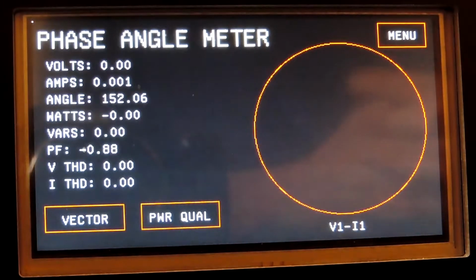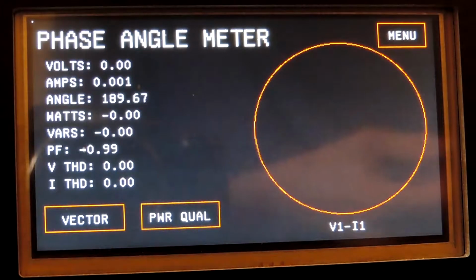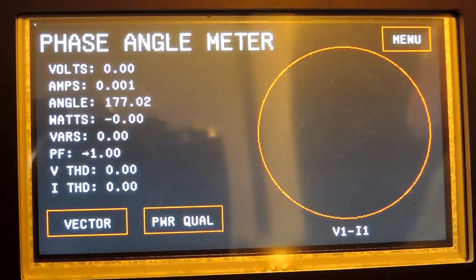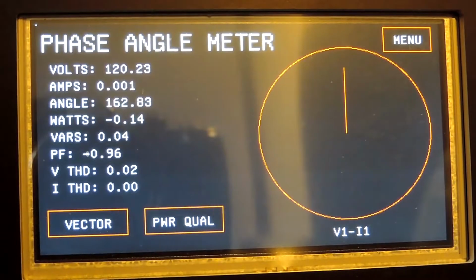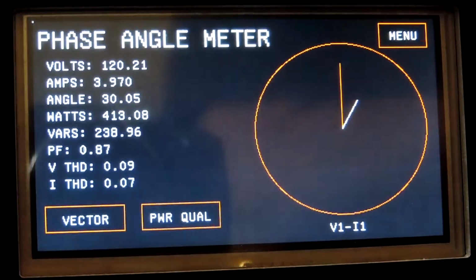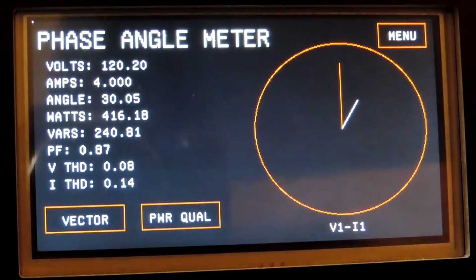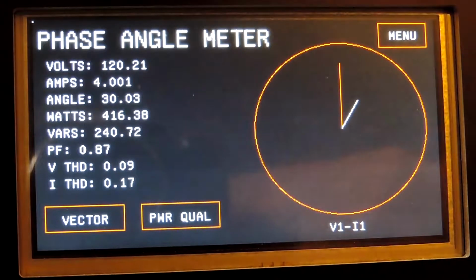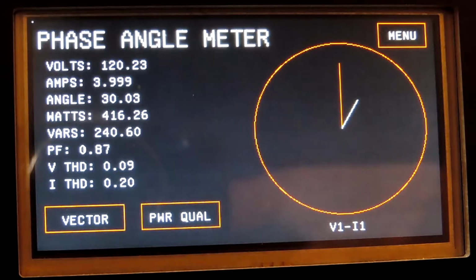Let's say that you replace the breaker. You have a transmission line that runs 15 miles from substation X to substation Y. You have replaced the circuit breaker at one end, substation Y, and as a final check, you want to make sure that the instrument transformers are connected correctly where you replaced the breaker.